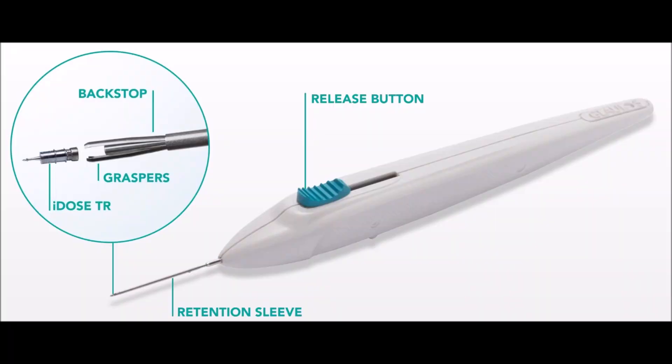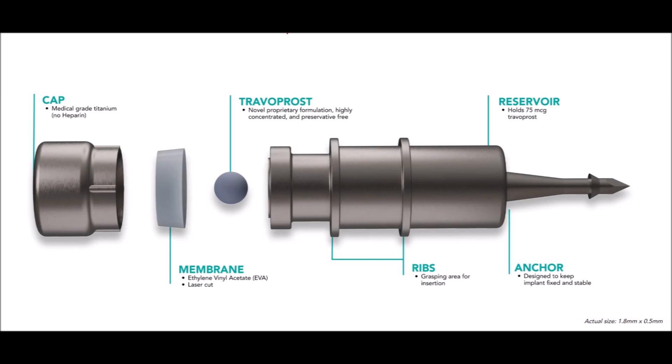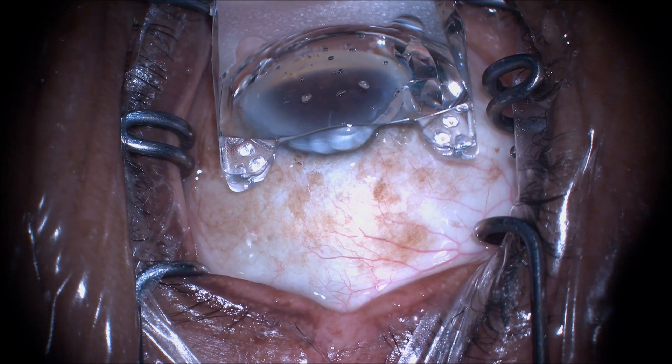This is the insertion device. It's important to learn to keep the release button locked forward when starting the procedure. This is a schematic of the iDose TR showing the anchor that will place it through the trabecular meshwork and anchor it in the scleral wall.